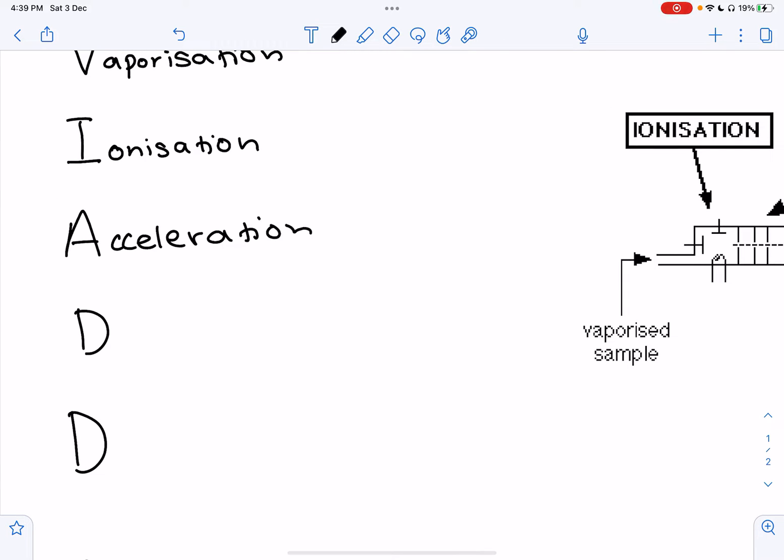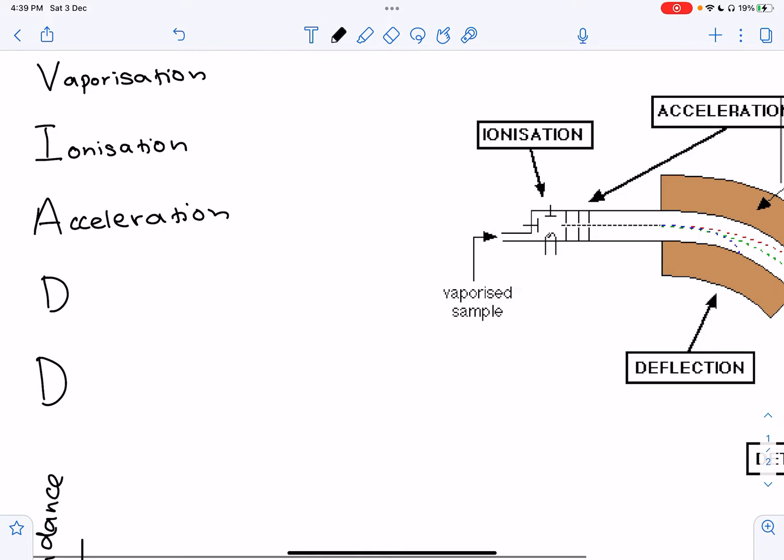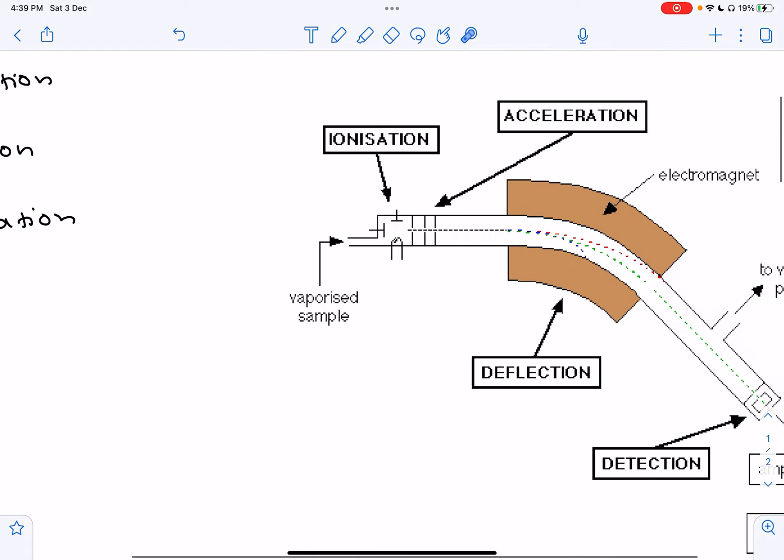The positively charged ionization chamber repels the positively charged ions, which accelerate towards the negatively charged plates. The speed at which they accelerate depends on their mass. The lighter ions move faster than the heavier molecules. This happens in the ionization chamber, and this is where they will then accelerate.